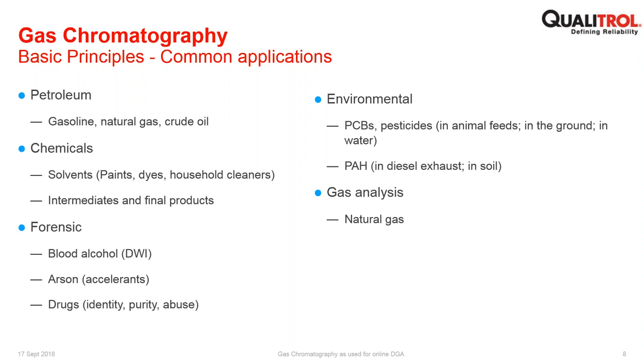So there is natural gas, and then the one that we are interested in, which is transformer dissolved gases. 9 different gases, 7 of them considered diagnostic gases, and then oxygen and nitrogen, the atmospheric gases. I just noted here that if you reference any of the standards relating to dissolved gas analysis for transformer oils, they of course call out gas chromatography as the analytical technique to be used. So that's IEC, American Standard Test Methods, and IEEE. And going through those standards, they all detail the use of gas chromatography. So it is the established technology for dissolved gas analysis. It's not the only one, but it is the original one, and it does provide some unique benefits.